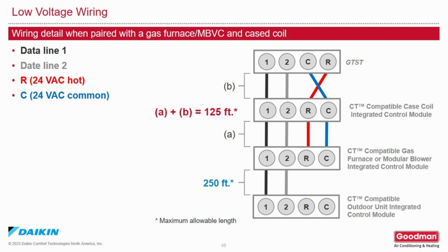The low voltage wiring detail when you're paired with a gas furnace, thermostat, and a cased coil. From the furnace to the cased coil to the thermostat, wiring should be a maximum of 125 feet. You will see that you do have an R and a C wire between the furnace, coil, and thermostat to carry power. Wiring between the indoor and the outdoor unit carries communication only and is limited to a maximum of 250 feet. Communication is established from the outdoor unit. Communication circuit should be a daisy chain between the outdoor unit, indoor unit, coil, and the thermostat.